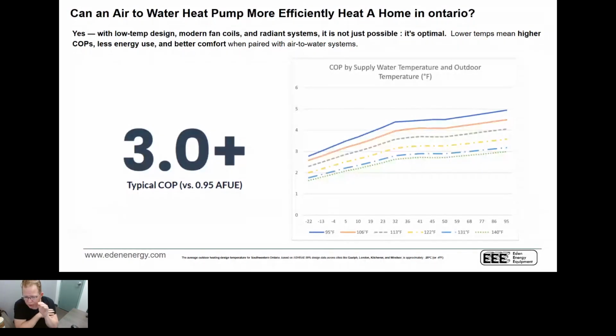That is very, very hot, right? If we were to compare that to a traditional air handler at 140 degrees, we'd be way down here. Hopefully you can see my mouse okay, right? At 140 degrees, we would have less than a COP of 2. So comparable to other heat pumps. But I want you to keep this 95 degree number in mind, because typically people see that 95 degrees and go, whoa, what's going on? I can't possibly use 95 degrees to heat the space. And the reality is we potentially can. I'm going to walk through a scenario where we could potentially achieve that and how it has a massive impact on what we can do from a heating and efficiency standpoint in the space.